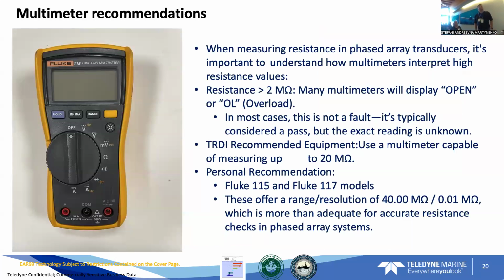All right, so when using a multimeter, our manual says when measuring the resistance in a phased array transducer, it's important to understand how multimeters interpret high resistance values. For resistance greater than 2 megohms, many multimeters will display an open or OL overload. I love this about our manual because it says in most cases this is not a fault. It's typically considered a pass. But seriously, how are you going to know what it is?